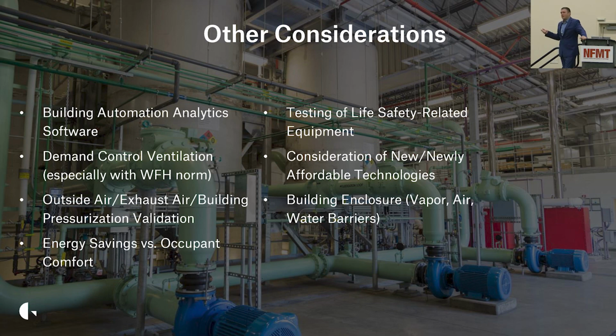Building enclosure. A lot of times people think they have a building enclosure issue when they have moisture and mildew problems in their facility. But from what I've seen, the first thing you need to look at isn't the building enclosure, it's the pressurization of the building. As long as you have a positively pressurized building, it might be leaky, but you want the conditioned air blowing out, not the unconditioned air sucking in. Still, building enclosure is a consideration, and that's a service many commissioning agents offer.